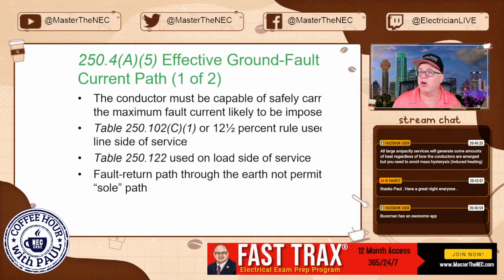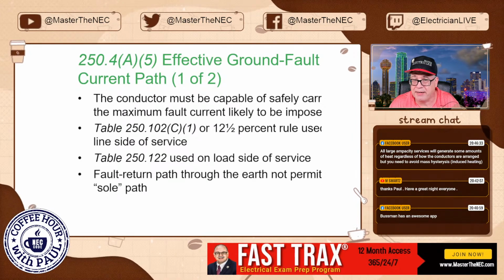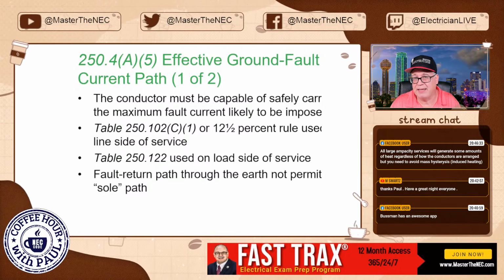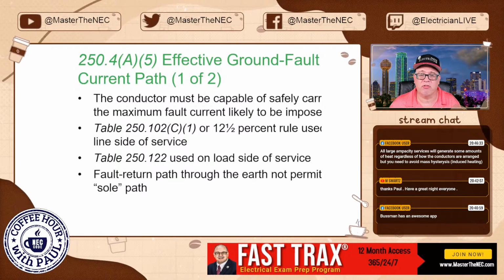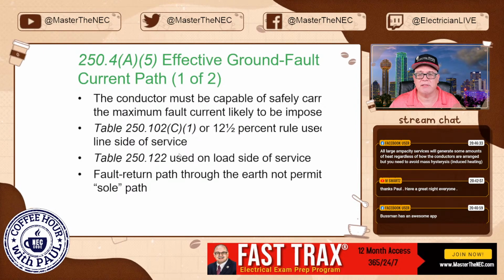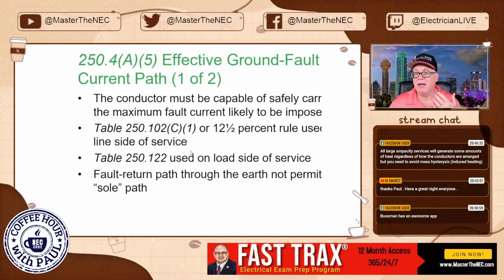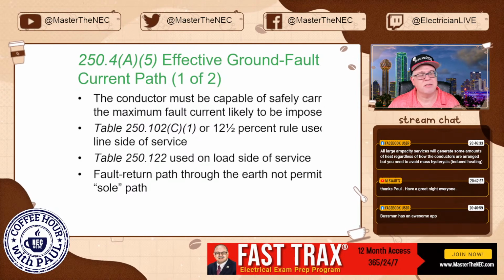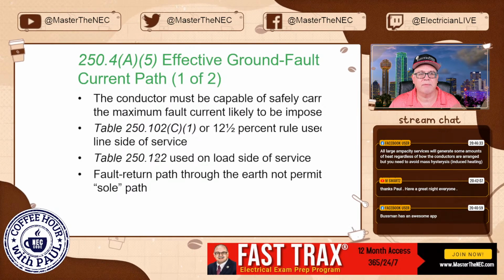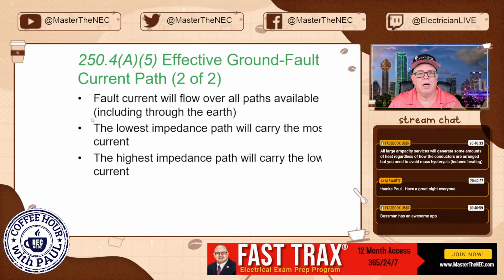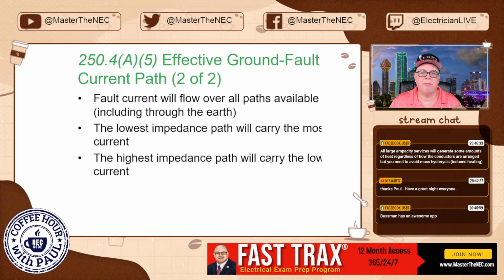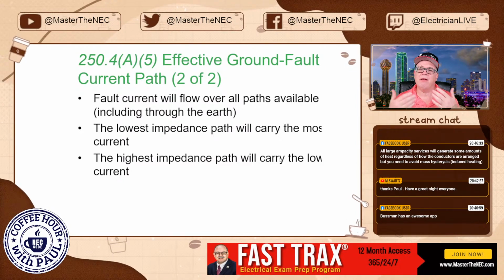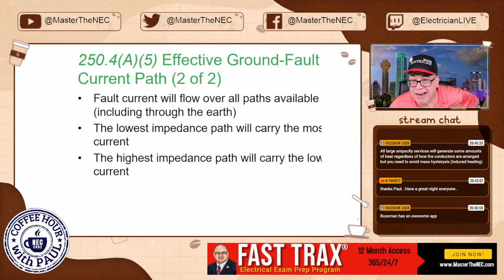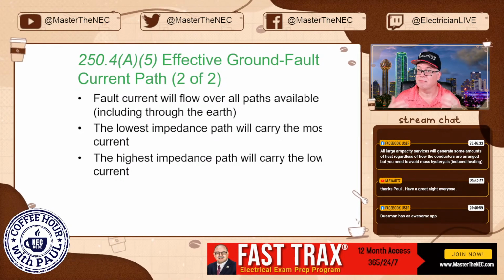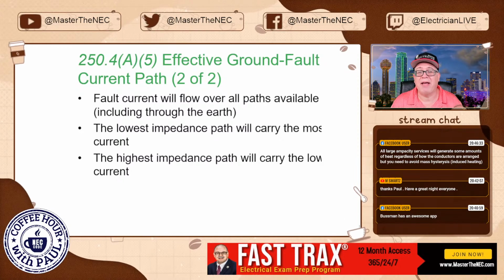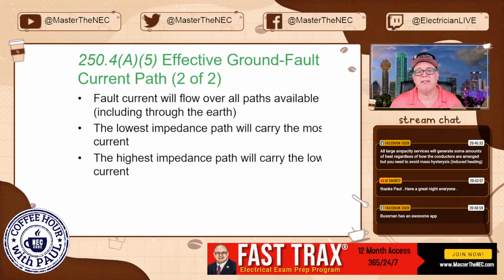So some will travel on the earth, but the majority of it's going to travel on that intended, constructed, purposely equipment grounding conductor out to that remote distribution panel. Okay, and that's what's going to clear your overcurrent device. Even though the earth is there and it seems to be in parallel, not going to use the earth as a sole means for doing that. Fault current will flow over all paths available. We just talked about it. It will go through the earth, but again, the lowest impedance path is going to actually carry the most current. So we understand there'll be other paths. But that lowest impedance path is going to carry the majority of the current.